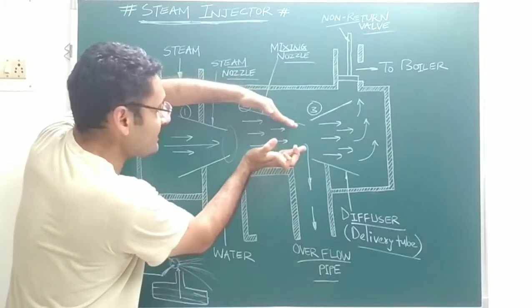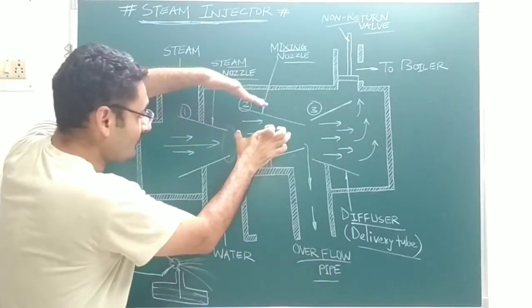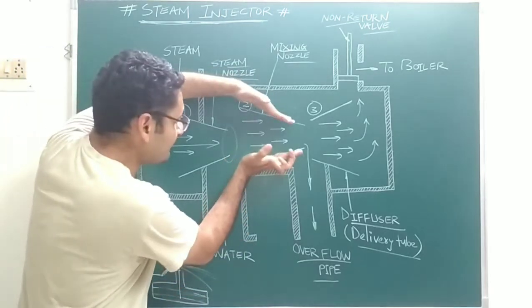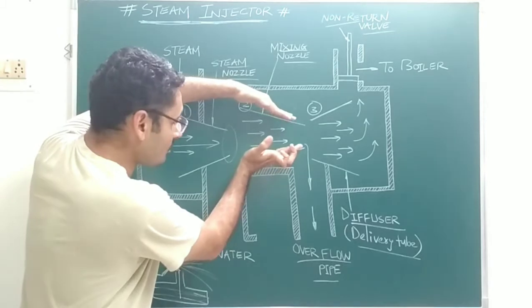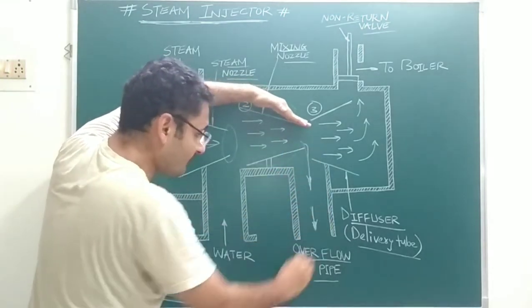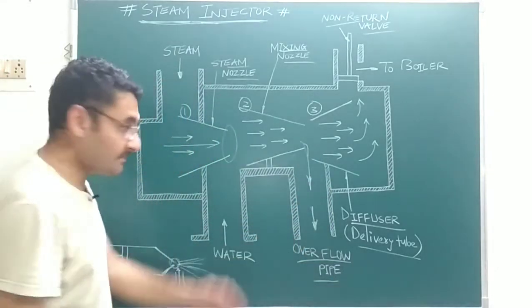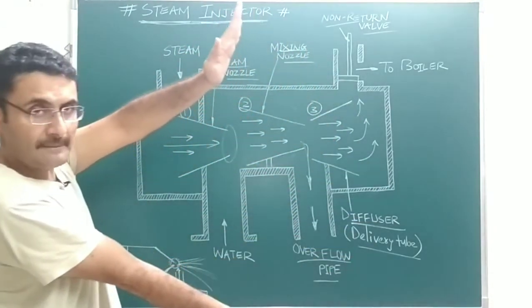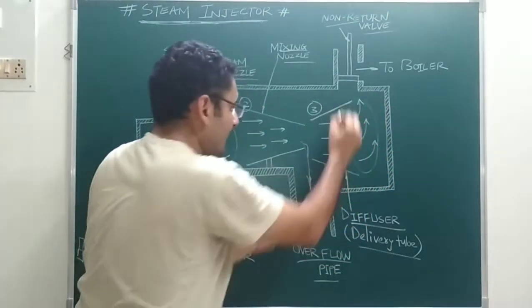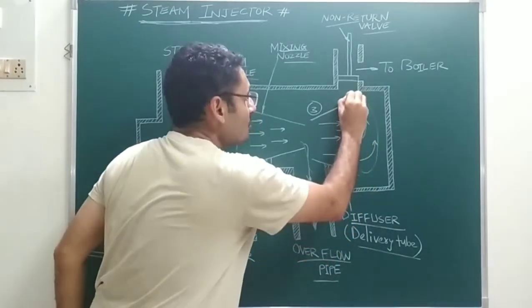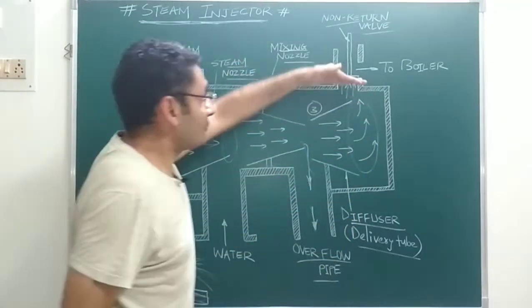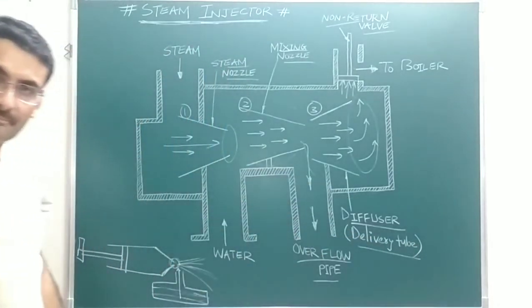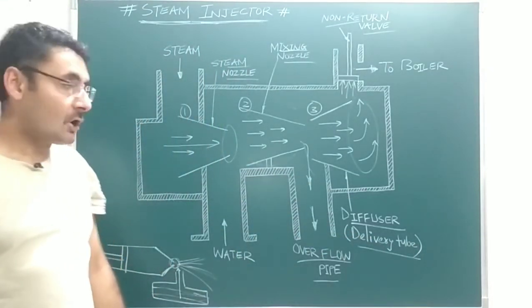Steam and water both mix in the mixing nozzle. Inside the mixing nozzle, the steam cools down and condenses into water, so extra water is present. Some of that extra water is removed through the overflow pipe. The remaining water enters the diffuser or delivery tube, which increases the water's pressure at the outlet. This high-pressurized water applies force on the non-return valve ball upward, lifting it, and high-pressurized water is supplied to the boiler.